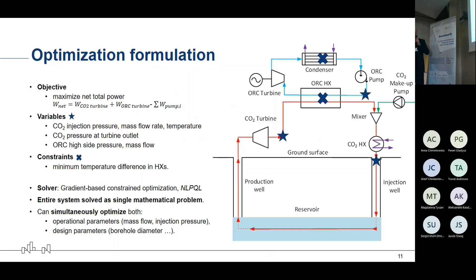When we look at the well and reservoir calculation, as my colleague already mentioned, we are working with the added value of the pressure difference. We basically have a thermosiphon effect, which we first of all utilize to avoid being forced to add an additional pump before the injection well. This allows us to avoid extra investment cost, and also get better overall efficiency, which we also try to check beforehand.